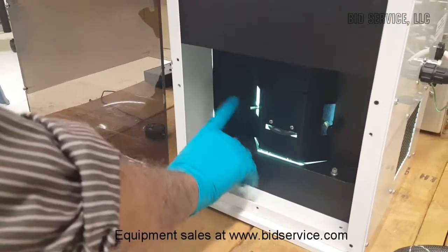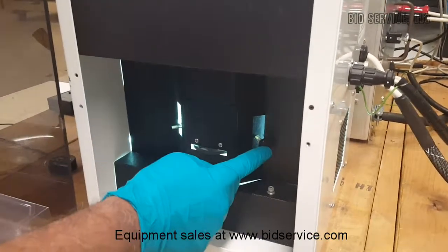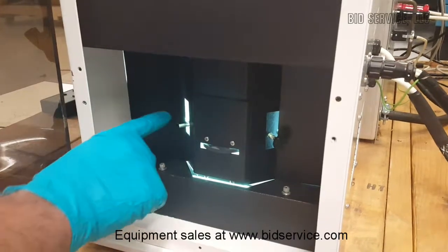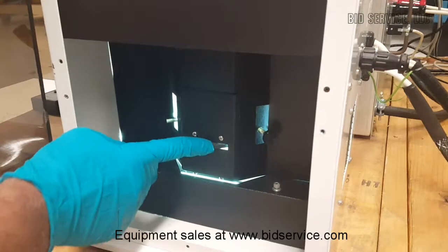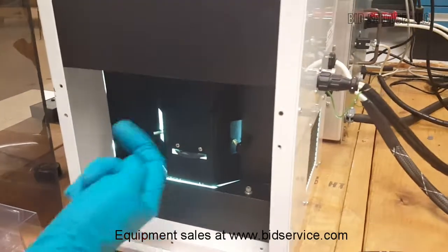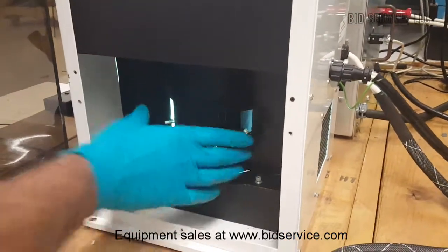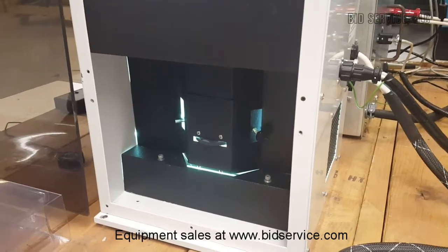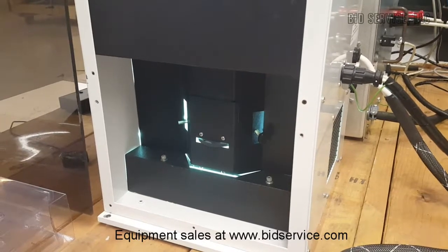And these are the knobs. There are two knobs, 1 and 2. These two knobs will adjust the position of the lamp in the XY plane, whereas this big wheel here will lift the lamp up and down. The purpose of these knobs is to exactly locate the arc inside the lamp at the focus of the ellipsoidal reflector.